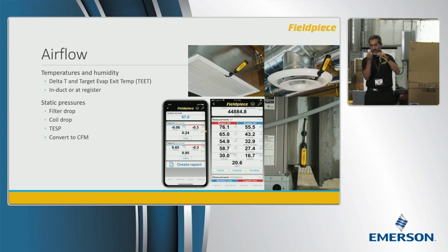In order for the manometer to take an accurate static pressure reading, there are holes on the side of a static pressure probe. You want the airflow to be going over those holes, not directly into the holes, which is why you don't insert the probe perpendicular to the airflow, but parallel to the airflow. Now, whether it's in or against airflow doesn't matter all that much, but against airflow is what most people recommend, and we'll just go with that.